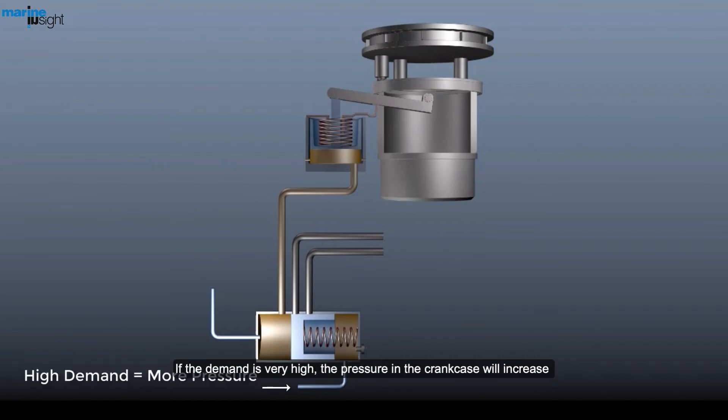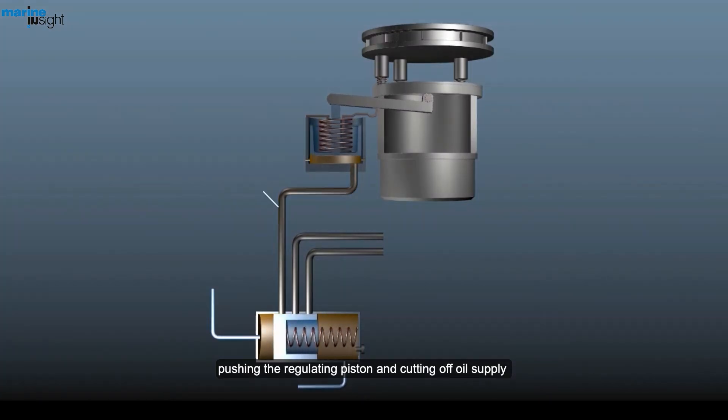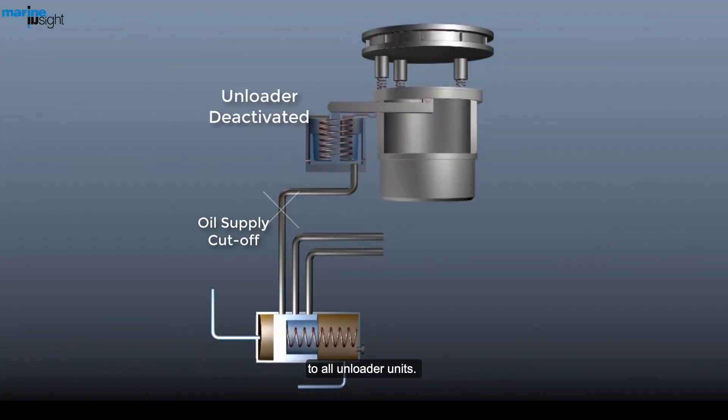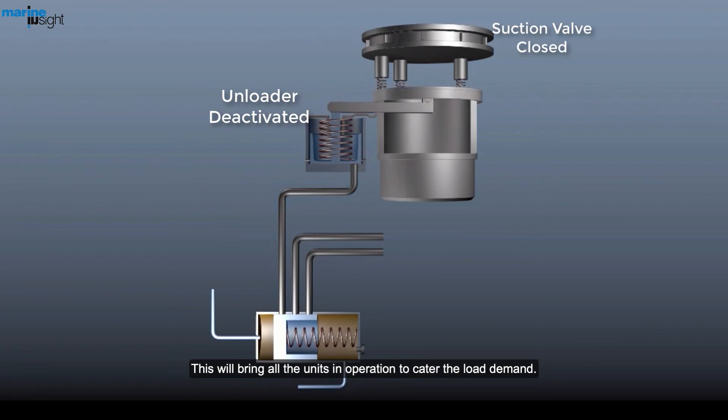If the demand is very high, the pressure in the crankcase will increase, pushing the regulating piston and cutting off oil supply to all unloader units. This will bring all the units in operation to cater the load demand.